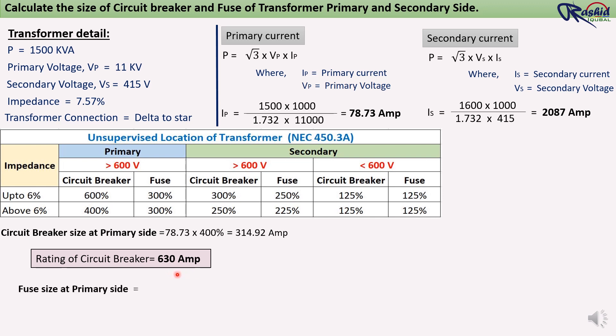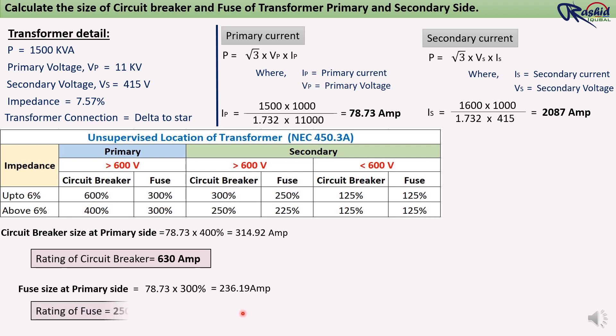For fuse calculation, we multiply 300% by the primary current: 78.73 × 300% = 236.19 ampere. So the fuse rating we will use here is 250 ampere.